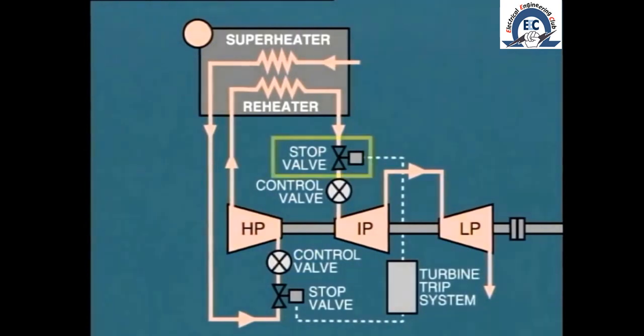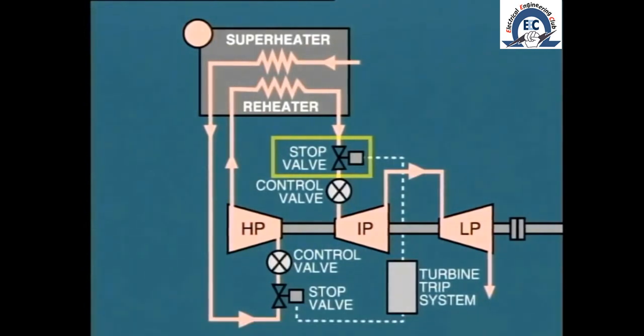So in normal operation, this reheat stop valve is retained in the wide-open position, like the main steam stop valve. If we wish to trip the turbine under any emergency condition, the trip relay is operated and closes both stop valves immediately.